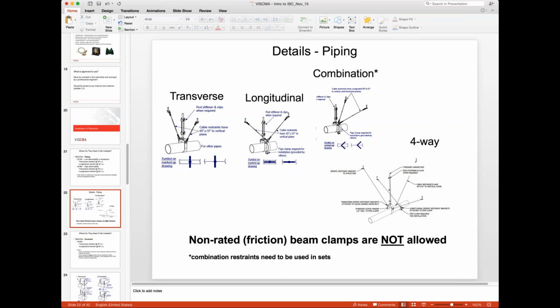When you do the math to determine the seismic force being applied — since the seismic force is a shear force — when these cables or rigid braces pull back that pipe in tension, there's a component in the vertical direction which will compress that hanger rod. More often than not, that's a relatively thin rod with a very long length, and under that compression load it will typically buckle. So most drawings, when done correctly, will have a rod stiffener of some means to prevent buckling of that hanger rod, and that's shown in all four of these drawings.